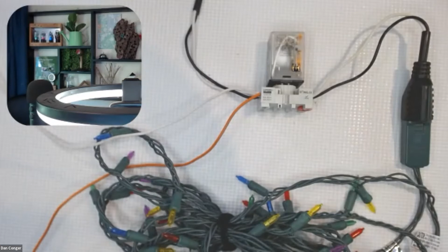So what it's going to do is take 24 or 30 volts from my bicoder, the low voltage, and then activate the high voltage. That's really what a pump start relay does - it takes a low voltage and then runs a 220 voltage, perhaps maybe a 120, maybe a 220, 240. It takes a higher voltage and a higher amperage rating and opens it in a safe way. It's how you can use low voltage to open high voltage.